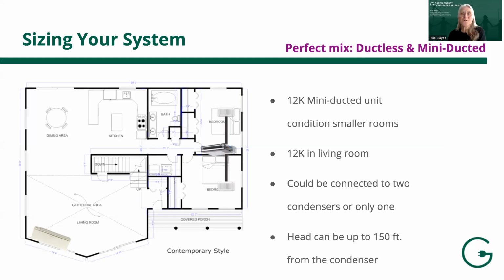Here's one potential solution for small bedrooms that are adjacent to each other, and that is a mini duct where you put an air handler in the attic above or the basement below, and you run tiny little duct work, 3 foot, maybe 6 foot duct work to reach into each room over a wall partition. And in this illustration, you've got 12,000 BTUs that split between the two. So they're perfect. They're getting 6,000 and they're happy as can be, and you're comfortable as can be. Now these two could be connected to 2 separate condensers or to 1 condenser. Generally, a condenser will work most efficiently when it has fewer heads on it, but you can put up to 4 or so heads per condenser, and the heads can be up to 150 feet from the condenser. So yeah, it's an option to do it either way.